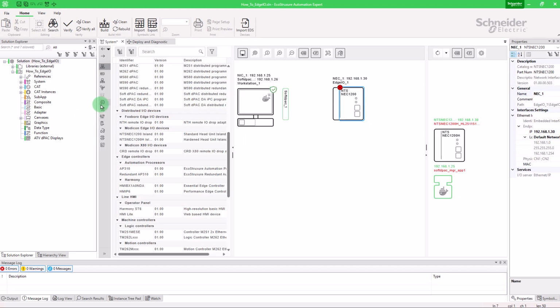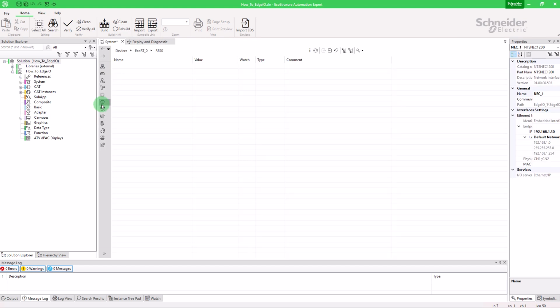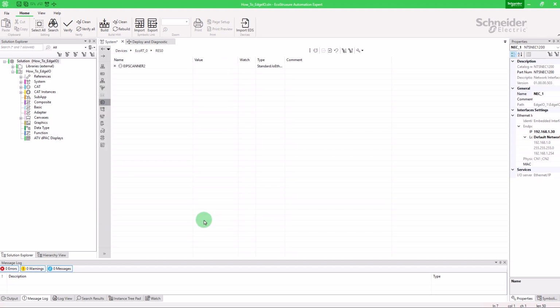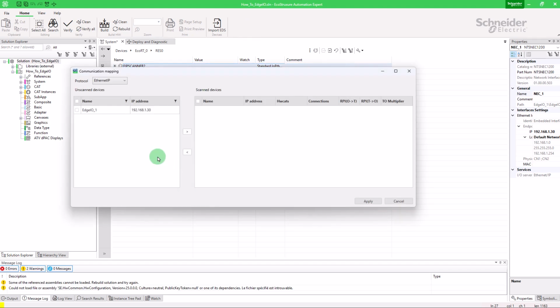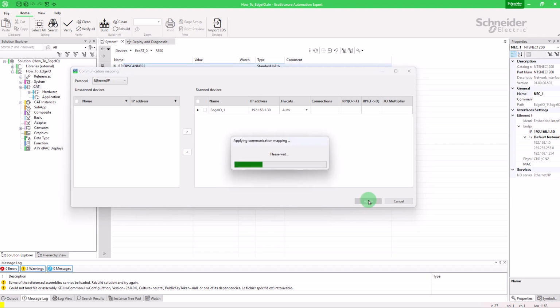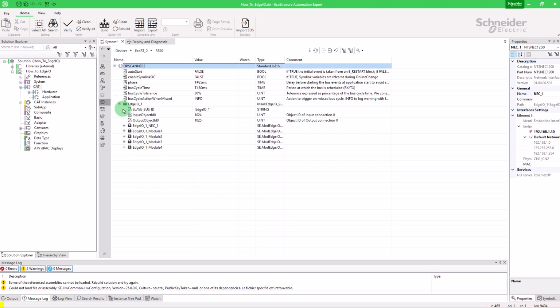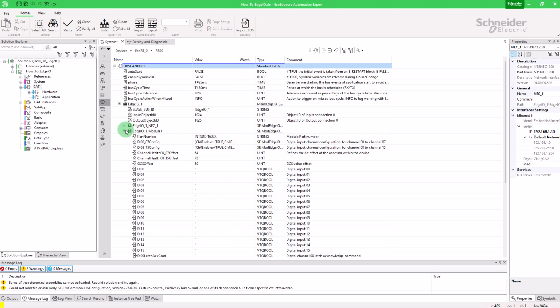Next, go to the hardware configuration in EAE build time. Add a new master, HW-CAT. Then add EIP Scanner 2. Right-click EIP Scanner 2 and open the communication wizard. Add the detected island to the list. All modules that make up the island will now be available for assigning symbolic links.